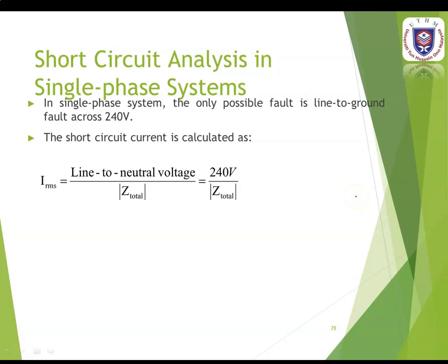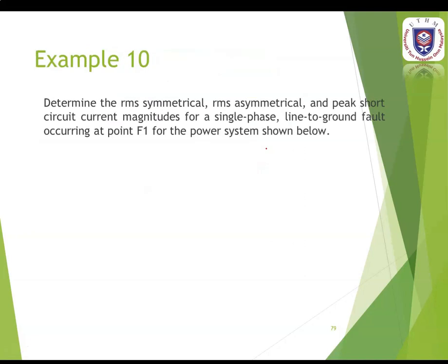We continue with the short circuit analysis in single-phase systems. In a single-phase system, the only possible fault is a line-to-ground fault across 240 volts. The short circuit current is calculated as IRMS = line-to-neutral voltage (V-phase) divided by the magnitude of the total impedance. V-phase must be 240 volts for single-phase. Example 10: determine RMS symmetrical, RMS asymmetrical, and peak short circuit current magnitude for a single-phase line-to-ground fault at F1.